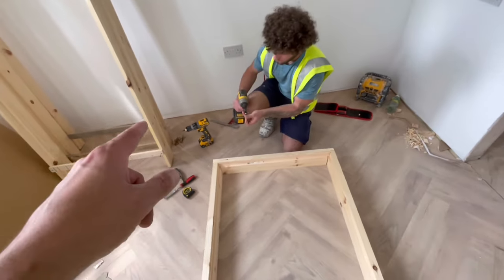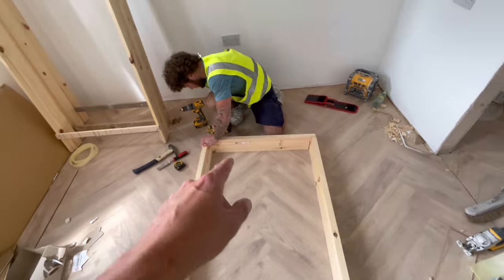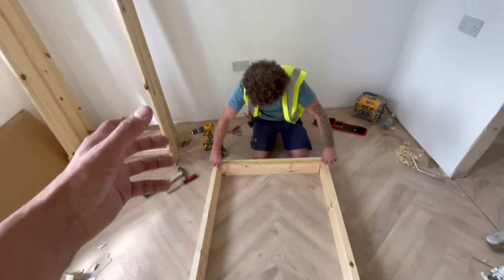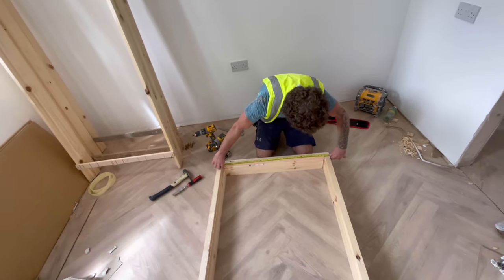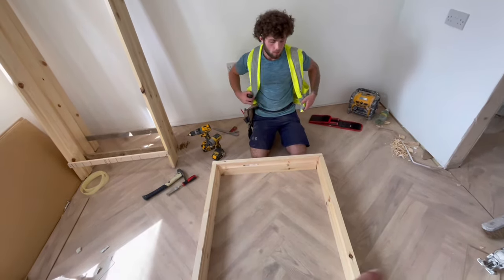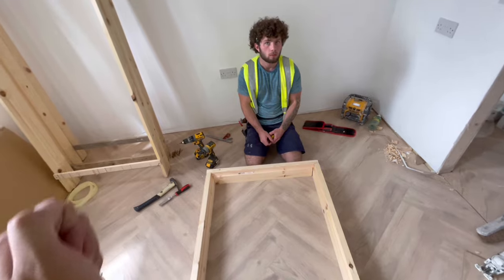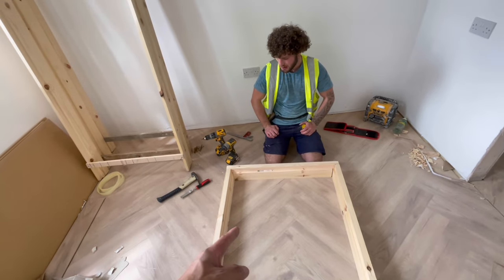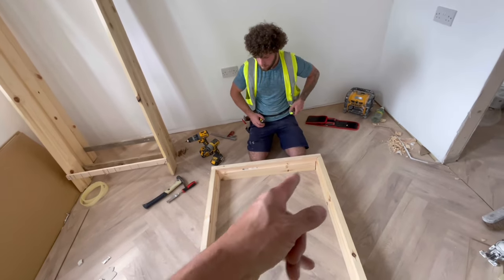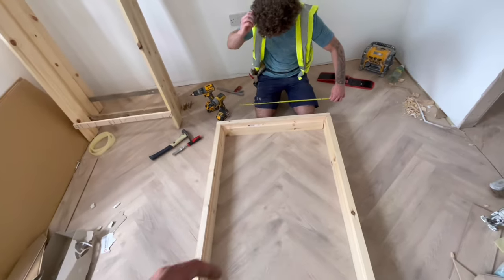The only problem is, because you're putting screws in the top there, if the top is out slightly, you'll just have to take the screws out the side and then bring the door out, take the top off and widen it a bit, if you know what I mean. But when we get this measurement, we'll just stick with that for all the other jobs then. So if we do it now and it's brushed and we go to close it and the brushes are a bit tight, we'll know, right, do it a bit bigger. If it's not brushed, we can do it a bit tighter in terms of the millimetre gap. But we can only go another 4 mil past that anyway, because 4 mil around the outside of the door is what we're allowed for fire regs.